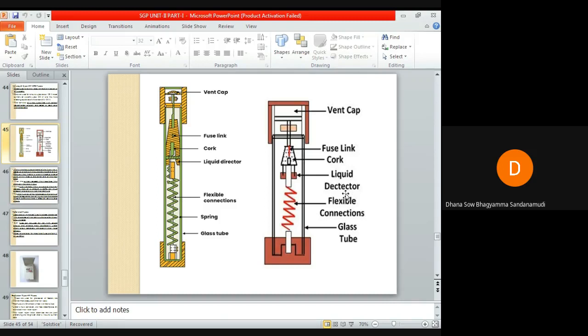So this is the liquid director. What happens is, as soon as the arc is struck here, the spring, which was held in position because of the fuse wire, just shrinks as soon as the fuse is blown out. When it shrinks, the liquid director will push oil in between these two contacts. Because of the heat produced by the arc, some of the liquid gets vaporized surrounding the arc. These gases will surround the arc and act as the arc quenching medium, and the arc will be extinguished.